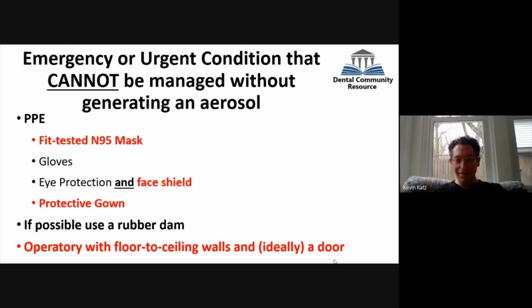To achieve that, and it's less typical in a dental operatory to talk about it, but in a hospital room, which is where we tend to have these airborne isolation infection rooms, AIIRs, essentially there's a door, and the door has to have sweeps on it, not sealed, but sweeps, so that it can pull air through the outside margin of the door. And you actually can have transducers which measure the pressure differential between the hallway and the room. And you need to have a negative pressure differential. You can test it with a smoke test, where you go by the edge of the door and release some smoke, and it pulls into the room. And essentially all of the exhaust is out through the bathroom, and the bathroom door is left open. So the flow of air is from the hallway into the room and out the washroom.